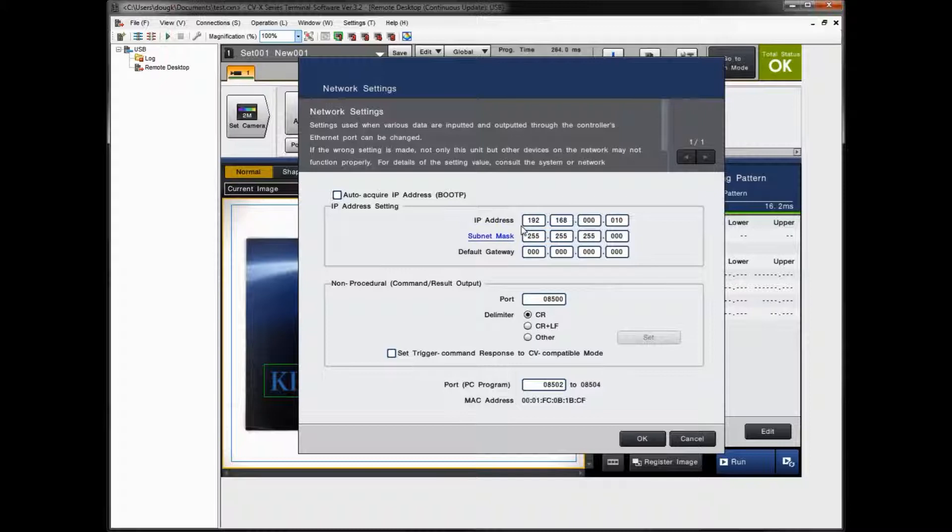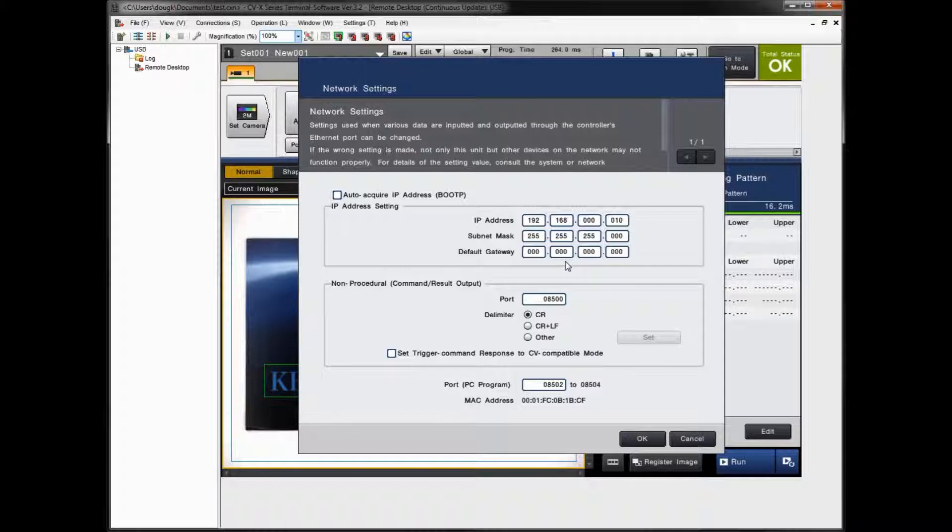This will be the IP address settings of the actual CVX controller. As you can see right here, this is the default setting out of the box. So as a default, it is 192.168.0.10. And you can see the subnet mask settings here. So this is out of the box. If you're going to use this connection or this IP address, you need to make sure your PC is set for a similar address.